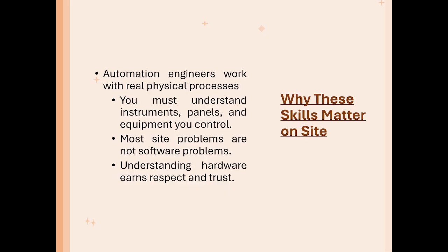Now on site, automation engineers deal with real physical systems: vibrations of pipes, motors overheat, instruments drift, and cables loosen. So most plant problems are not software problems. They are caused by wiring issues, instrument failures, grounding problems, air supply loss, or mechanical wear. Now, when you understand hardware, technicians actually respect you, operators trust you, and then supervisors rely on you. And this understanding begins with instrumentation, which is the plant senses.